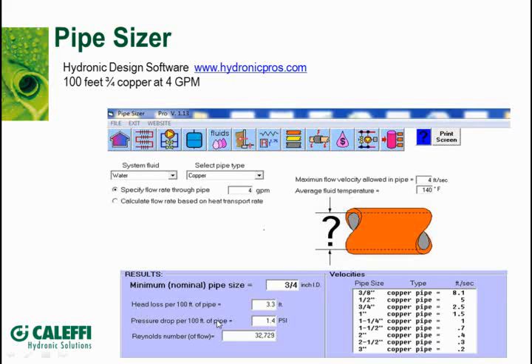So it's going to tell you what the head loss, what the pressure drop is per 100 feet of 3/4 pipe. So if you know how long your loops are, if you've got different size loops in the building, you can add all that up. You can calculate what the pressure drop is, and then you can use this little program here to make sure that you've got enough velocity going through that to push the air out of it. It's a great little program. The whole software is great, but I really like this module in it.